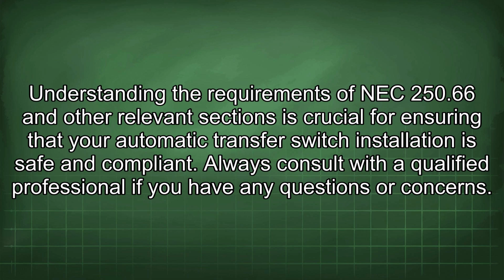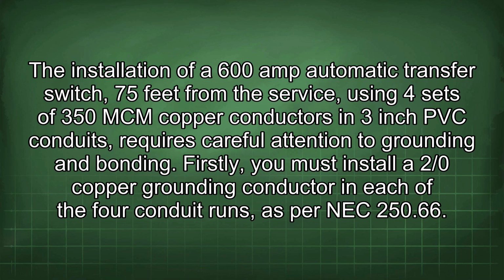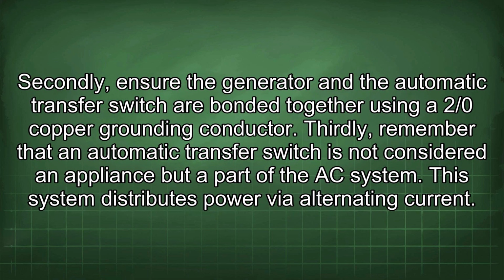Understanding the requirements of NEC 250.66 and other relevant sections is crucial for ensuring that your automatic transfer switch installation is safe and compliant. Always consult with a qualified professional if you have any questions or concerns. The installation of a 600 amp automatic transfer switch, 75 feet from the service, using 4 sets of 350 MCM copper conductors and 3-inch PVC conduits requires careful attention to grounding and bonding. Firstly, you must install a 2/0 copper grounding conductor in each of the 4 conduit runs as per NEC 250.66. Secondly, ensure the generator and the automatic transfer switch are bonded together using a 2/0 copper grounding conductor.